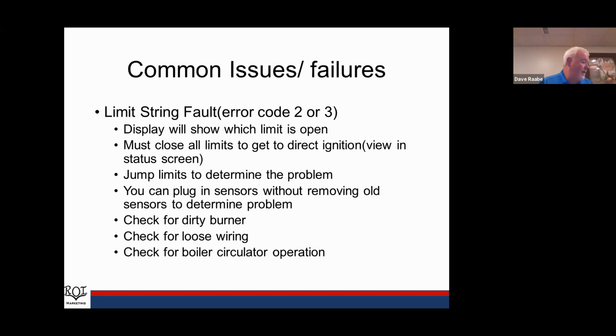The other thing that I wanted to mention is that if we get an error that says we have a sensor that's shorted, or we suspect a sensor, we can take a new sensor right here with the Molex plug, and without taking anything out of the boiler, just unplug the sensor that's in the boiler, plug it here, let it hang there, and then see if the boiler lights up and we see the correct values before we go changing parts out. So just another tip there.